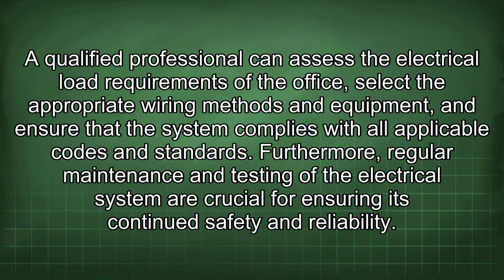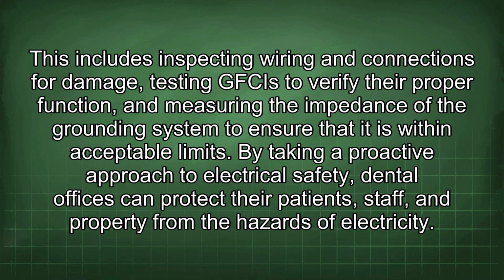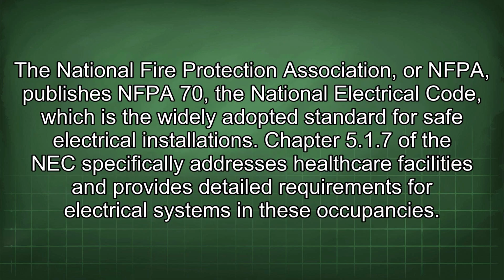Furthermore, regular maintenance and testing of the electrical system are crucial for ensuring its continued safety and reliability. This includes inspecting wiring and connections for damage, testing GFCIs to verify their proper function, and measuring the impedance of the grounding system to ensure that it is within acceptable limits. By taking a proactive approach to electrical safety, dental offices can protect their patients, staff, and property from the hazards of electricity. The National Fire Protection Association, or NFPA, publishes NFPA 70, the National Electrical Code, which is the widely adopted standard for safe electrical installations.